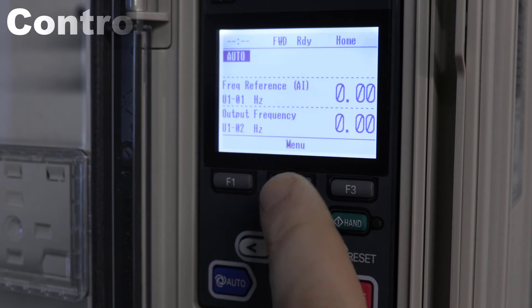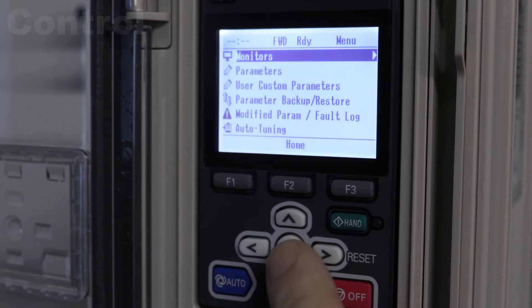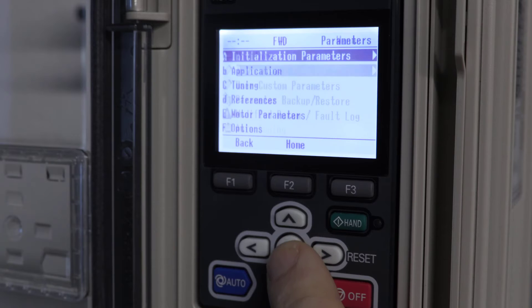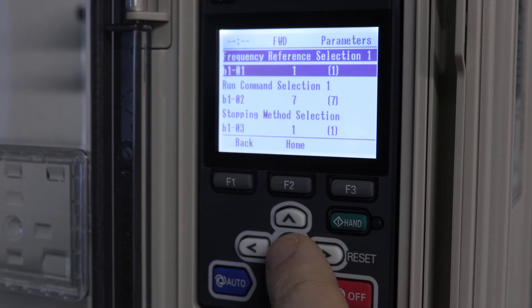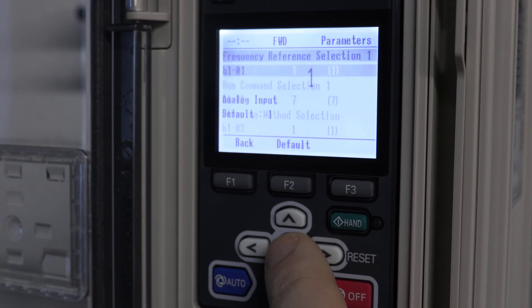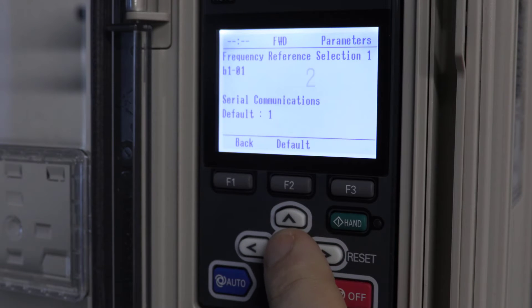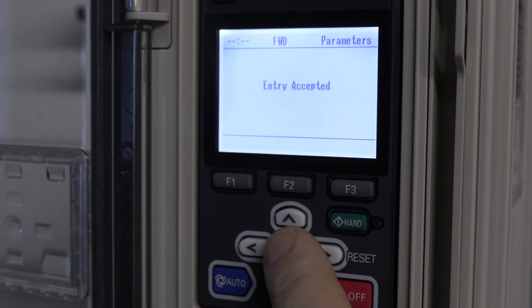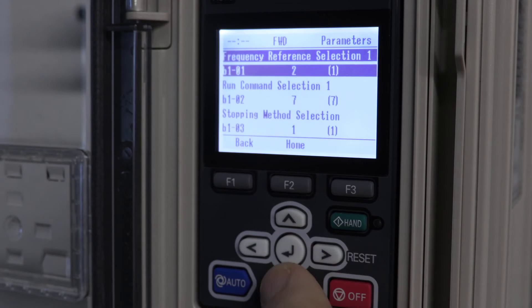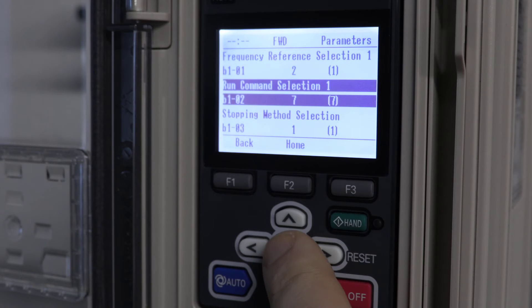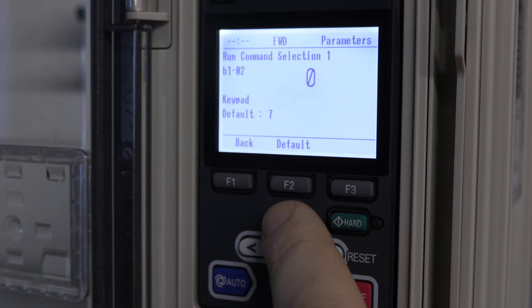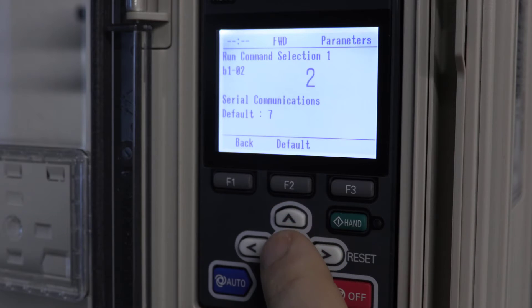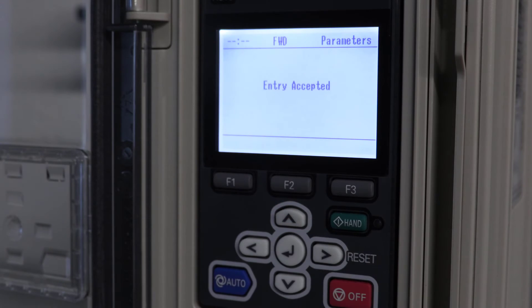Controlling an HV600 over BACnet couldn't be easier. Access the B1 parameter group and adjust B1-01, the frequency reference, and B1-02, the run command, to the serial communications option 2. That's it on the drive side. You are ready to send control commands over the network.